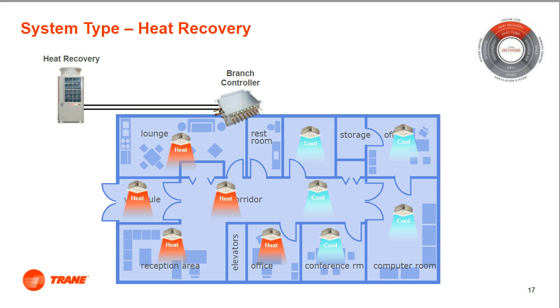All systems do have 2 pipes between the branch controller or heat recovery control unit and the zone terminal units. Finally, all VRF systems require the use of the manufacturer's provided system design software for pipe sizing and other system requirements.